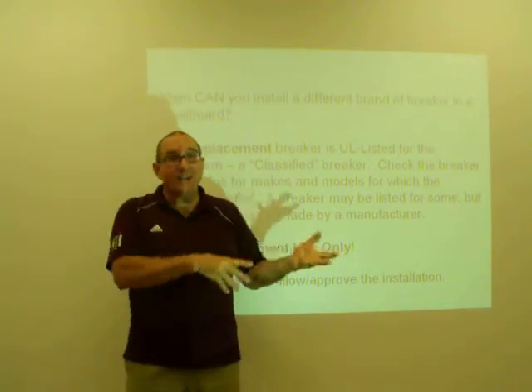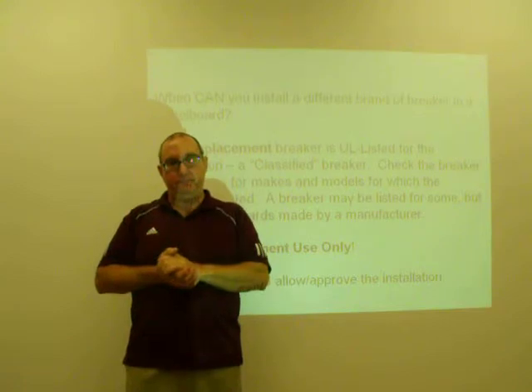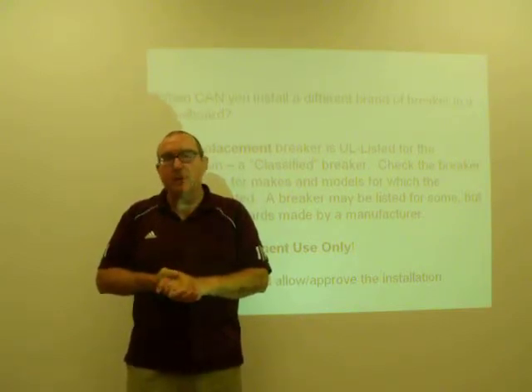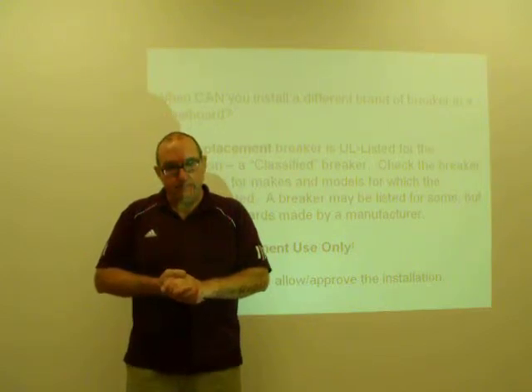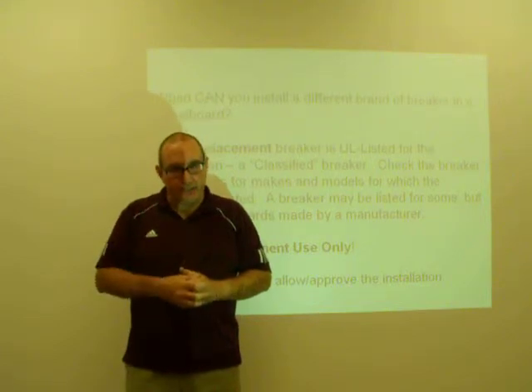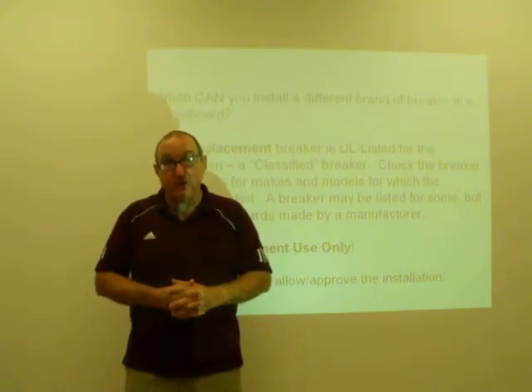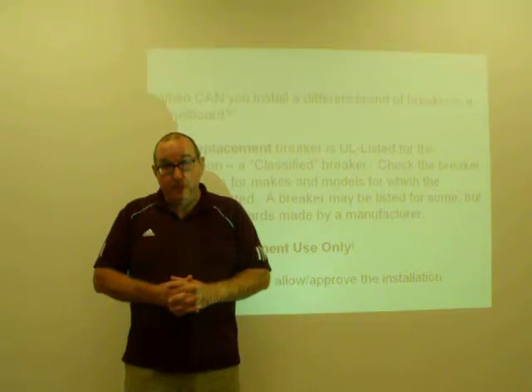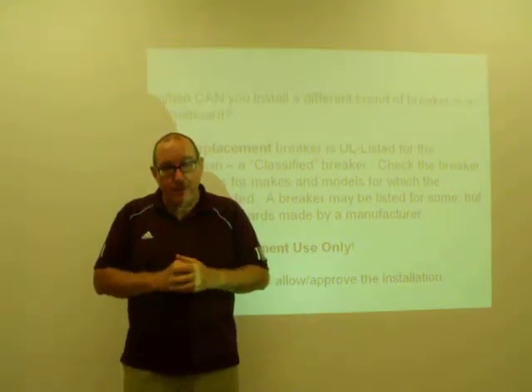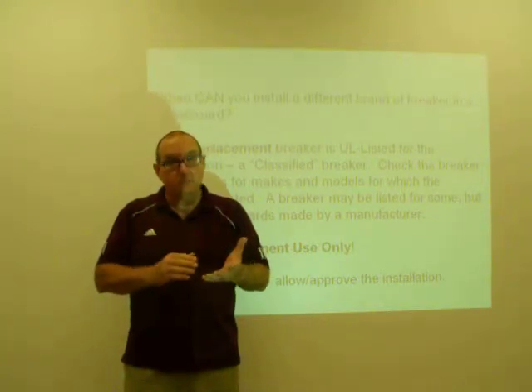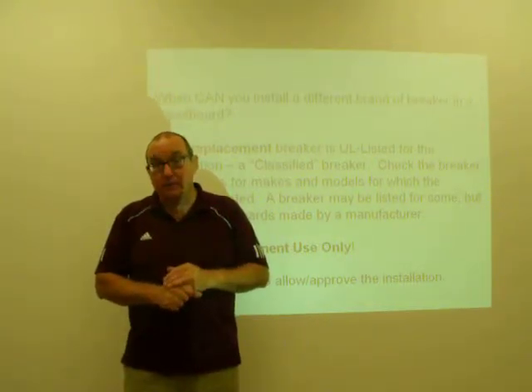So when can you install a brand X breaker in a brand Y panel board? One of the first conditions is typically these applications are listed for replacement use only. So you're on a service call, you have a bad breaker, you need to replace that breaker, as in the case of my friend's air conditioning system. You have a couple of options depending on the make and model of the original panel. Stock the original manufacturer's breaker, or go get one if you don't have it on your truck.